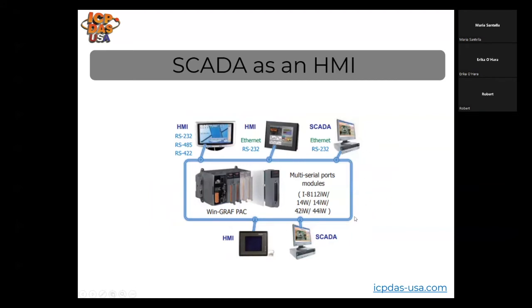Here's another snapshot of it. So basically you have one WinPAC controller in the middle. It's being controlled and monitored using an HMI. SCADA can also be used to data log. Another SCADA system can be used for showing the control plant, what's happening in the system, and various other functions and features. But essentially, multiple connections using either serial or Ethernet connections to the PAC will allow you to control, monitor, and do other functions from the data from the Win-GRAF PAC that's controlling the application.